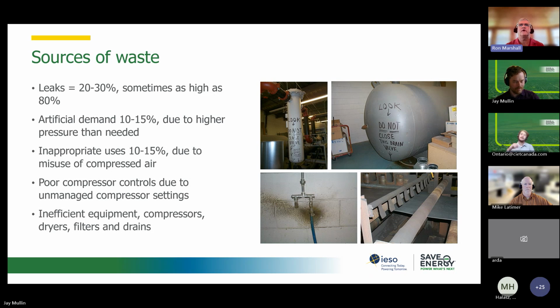There's various control modes. If you went to the Compressed Air Challenge fundamentals training, you would get a tutorial on the various control modes. So for some control modes, for every 10% reduction in flow output of the compressor, there's only about a 3% reduction in power. But say for a variable speed drive compressor, it's pretty close to a 1-to-1 relationship. So for every 10% reduction in flow, you get a 10% reduction in power. So those are two extremes on either side of the efficiency curves of compressors, right? And there's various control modes in between, like load unload, variable displacement, things like that.